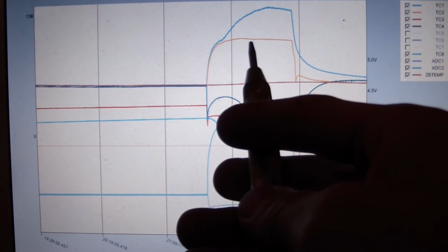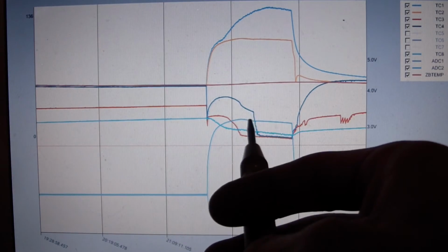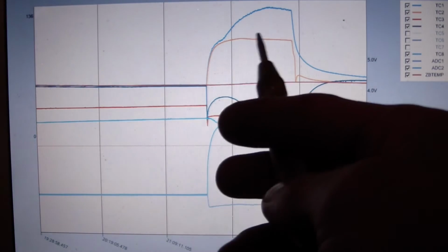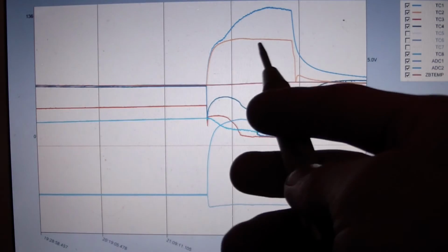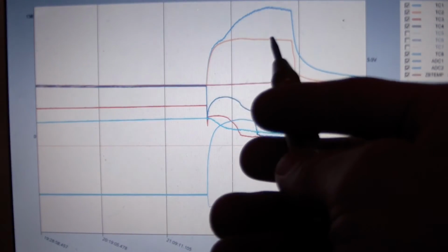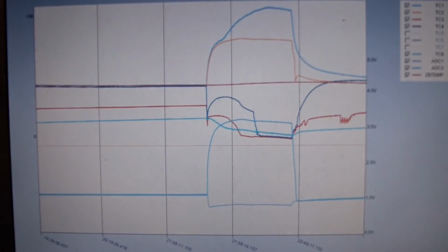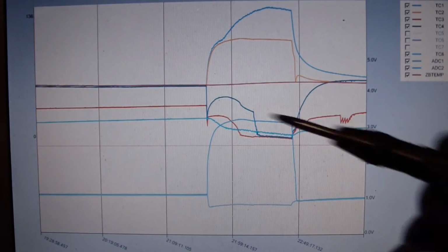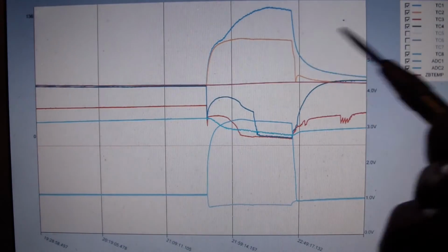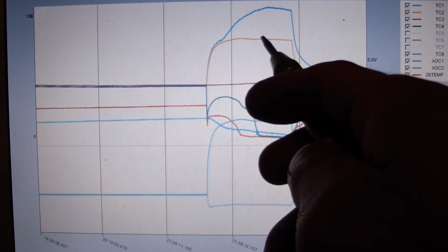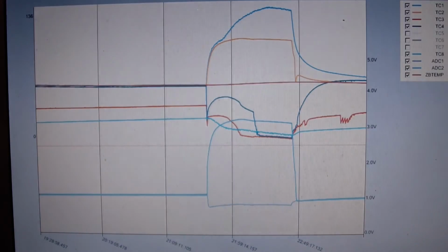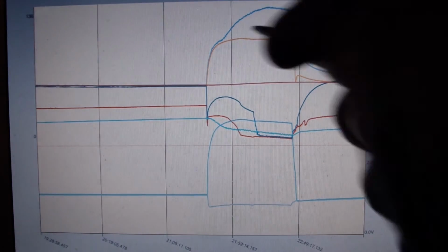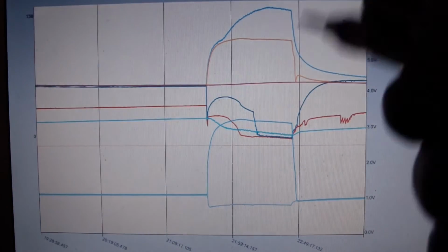Also seems to correspond to the subcooling temperature, because if you have a drop in high side pressure, all other things being equal, subcooling temperature is going to drop accordingly. If you have, say, a 10-degree temperature difference between ambient air and your saturation condensation temperature, then my subcooling is pretty poor. It's usually like 7 to 10 degrees below that. So those two lines track together relatively well.